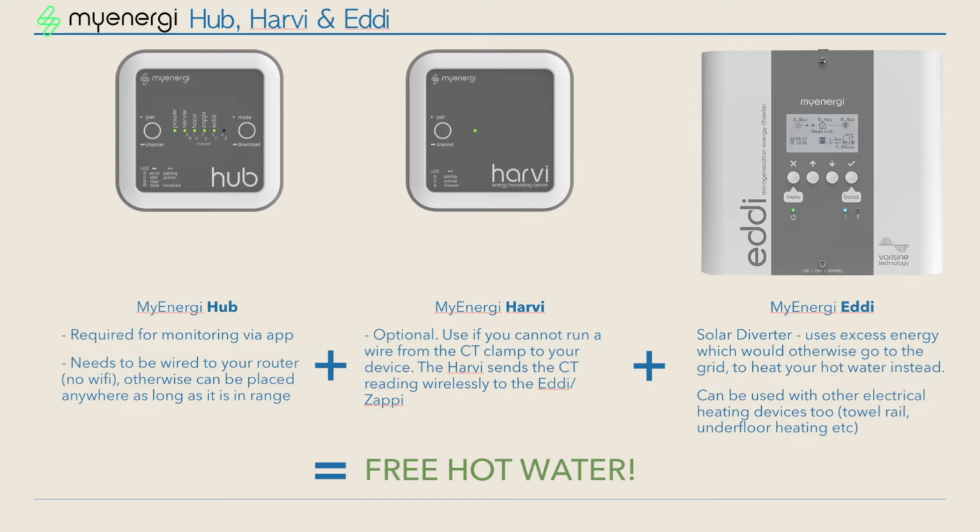Finally, then there's the main device that we wanted, which is the MyEnergi Eddi. Now, you could install this by itself without the other two things, right? You don't need the hub, that's just optional. And the Harvi, you don't need if you can find a way to hardwire the Eddi to the CT clamp, which needs to go around your main supply. So if your water tank, or wherever you choose to locate the Eddi, is in such a position that it's close to your main supply, or you can get a cable there, then brilliant, that's all you need.